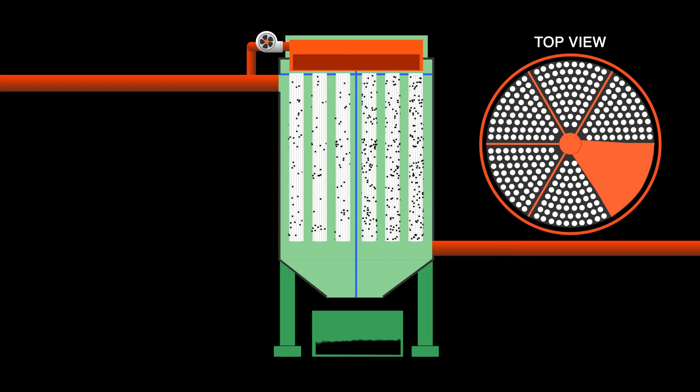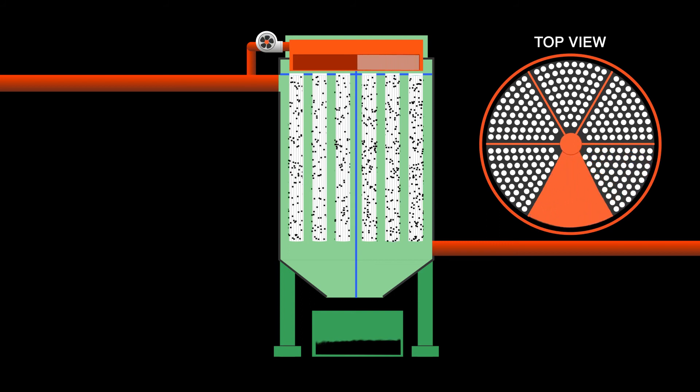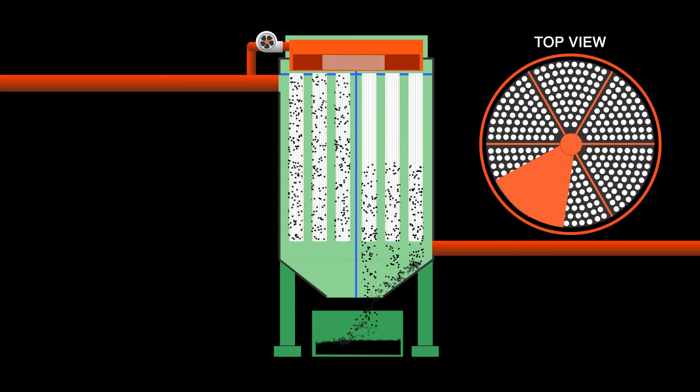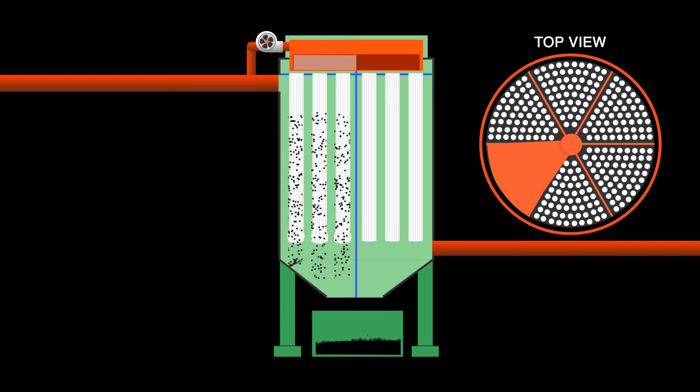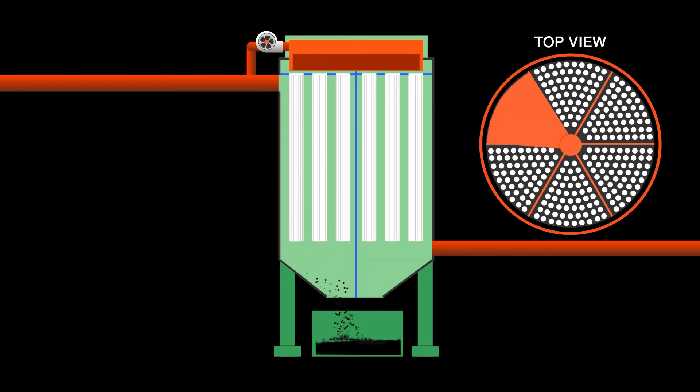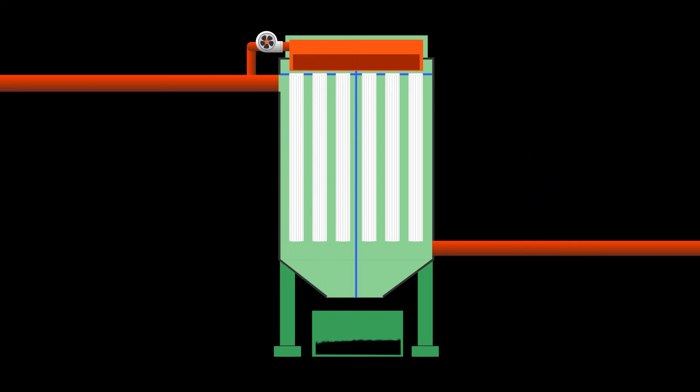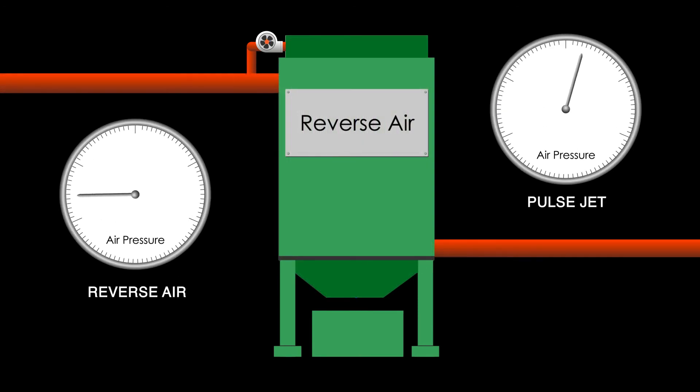For cleaning, reverse air generated by the equipment fan or medium pressure blower is directed by a rotating arm over the bag, blowing reverse air into them to remove dust. This type of reverse air baghouse generates a lower cleaning air pressure than compressed air pulses of a pulse jet.